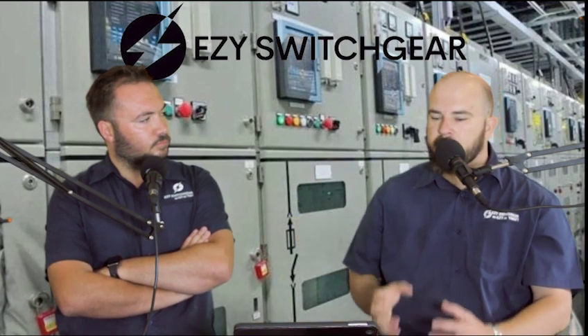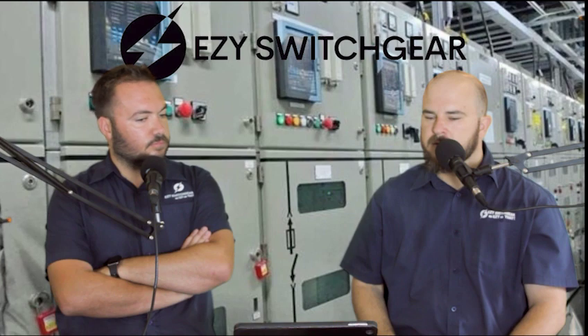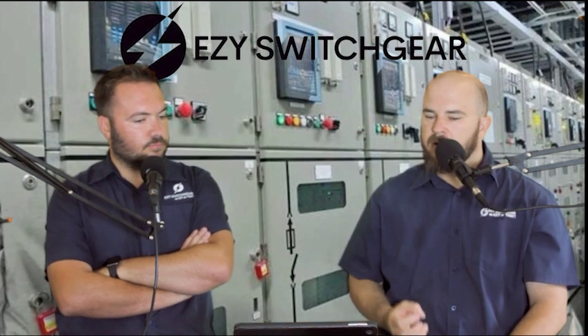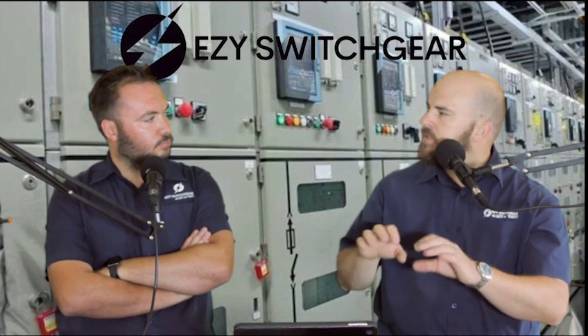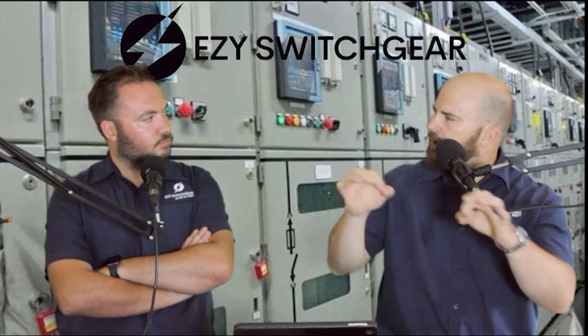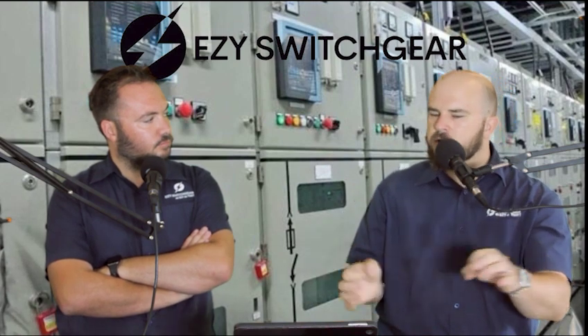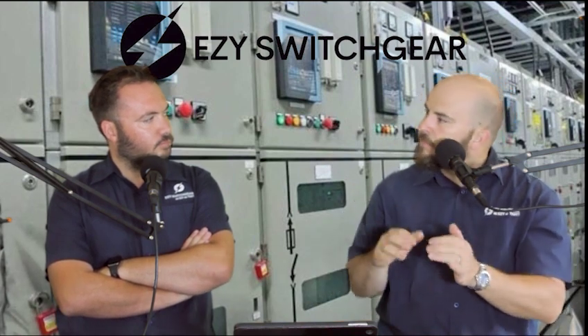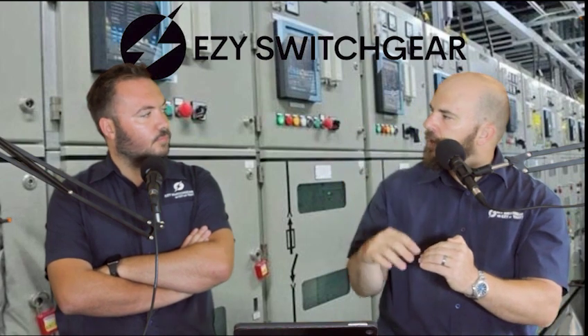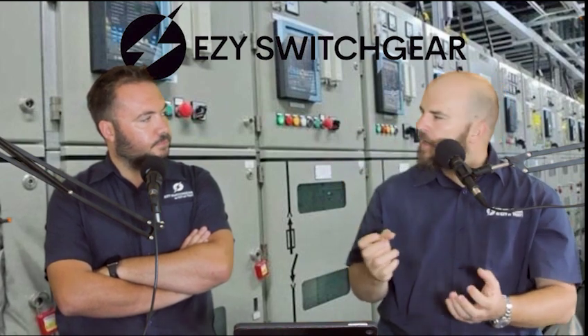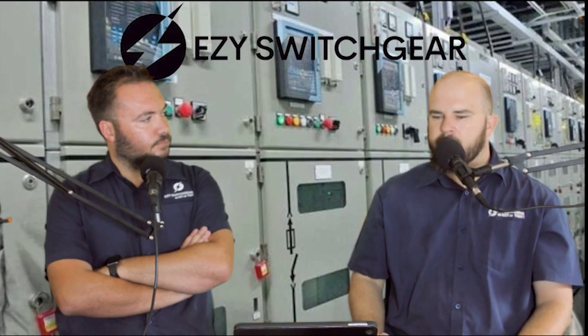So that is what the switchgear insulation is all about. Then on air insulated switchgear they always put something extra, an extra layer of protection over the bus bars, over everything, so that you can improve that basic impulse level. So they try and mitigate a lot of the issues, but it's not always possible.